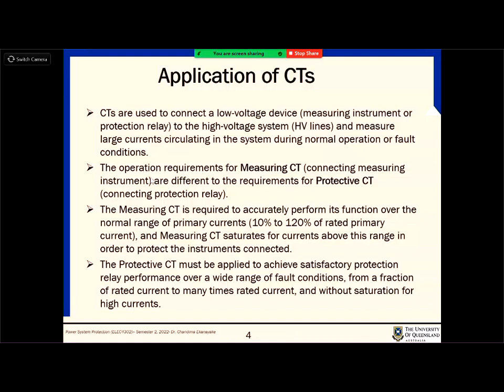The other one is not only that. If you go into a substation or a SCADA system, you will see that in this line 100 amps is going through, and in this transformer, when it is at full load, the current is this much. All that information is there. That is called measuring CTs. So you measure the currents going through the system. You have two types, measuring CTs and protective CTs, right? Out of them, which one needs very high accuracy?